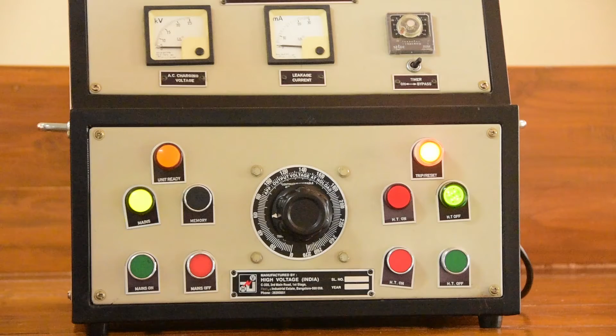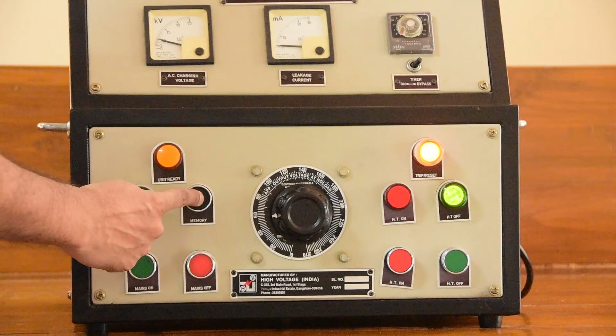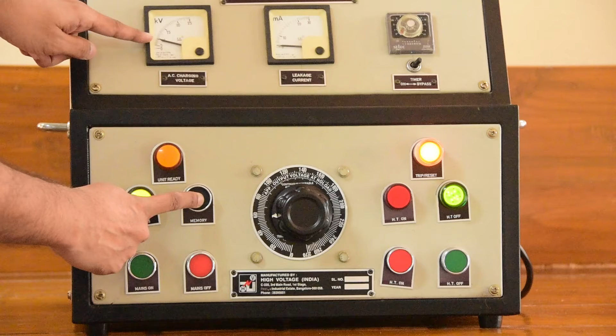Focus on this black colored switch - this is a push button that shows memory. Let us press the memory switch. As I press it, there is an arrangement inside that registers the last reading before the failure of the sample, along with the position of this dial. This position is now registered as the last position, presently showing 8 kV.